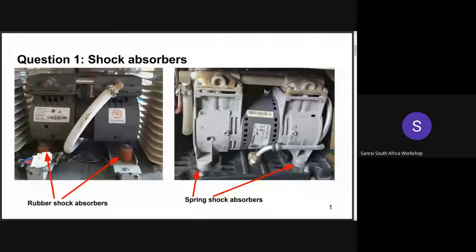The only component that vibrates in an oxygen concentrator is the compressor. The shock absorbers attached to the base of the compressor help to minimize compressor vibrations. Some possible causes include: shock absorbers loosely connected to the compressor; springs and rubber shock absorbers in some concentrators becoming weak, broken, or damaged; wrong shock absorbers installed during previous maintenance; and the compressor leaning on one side.